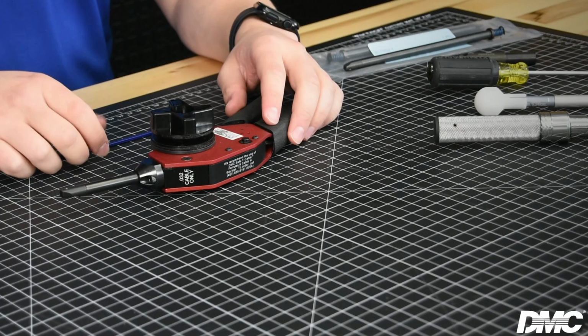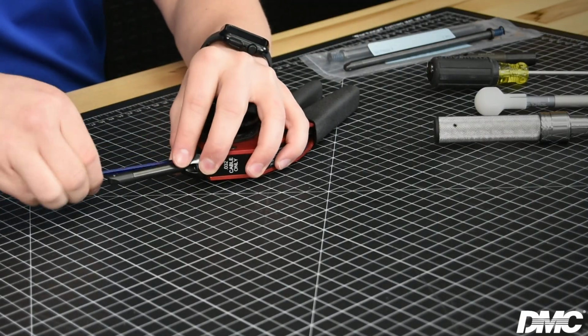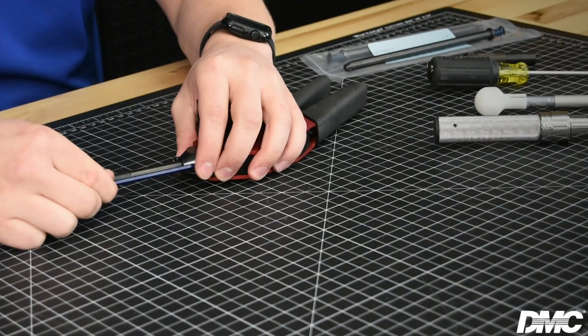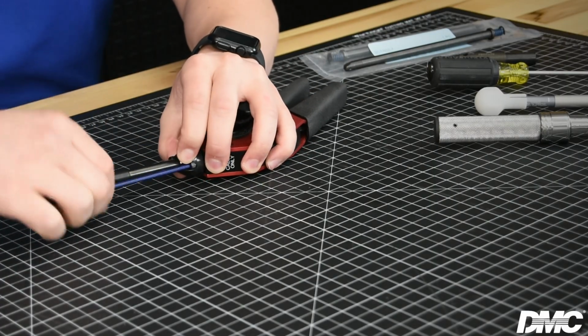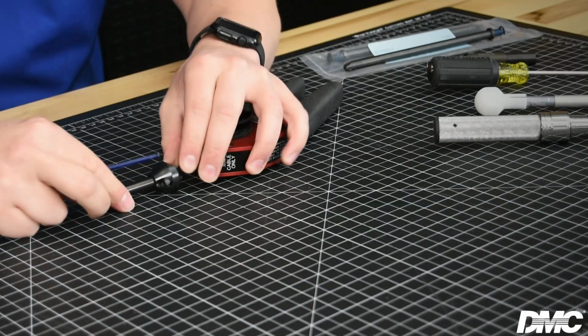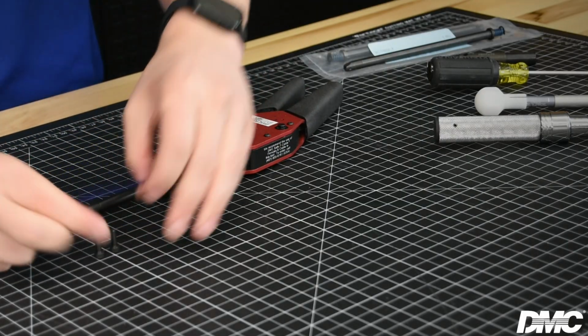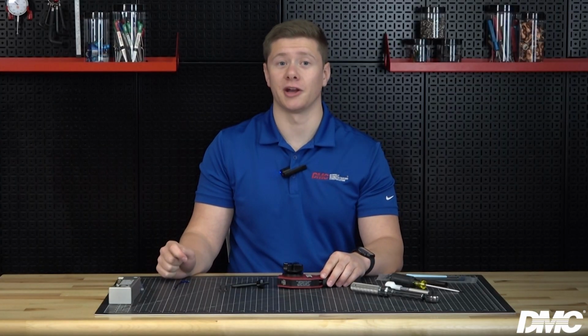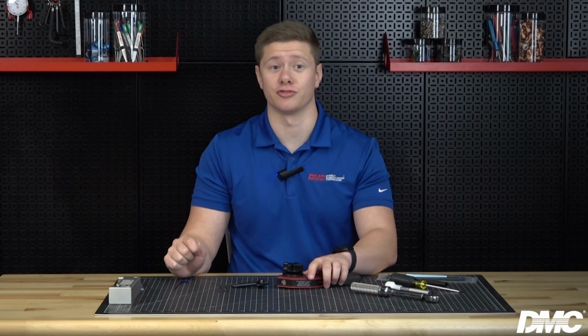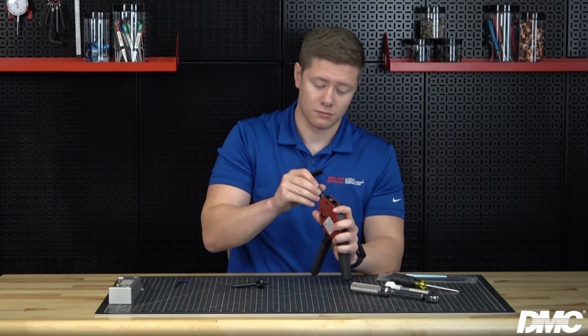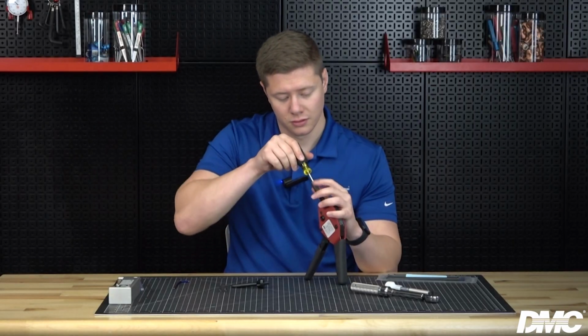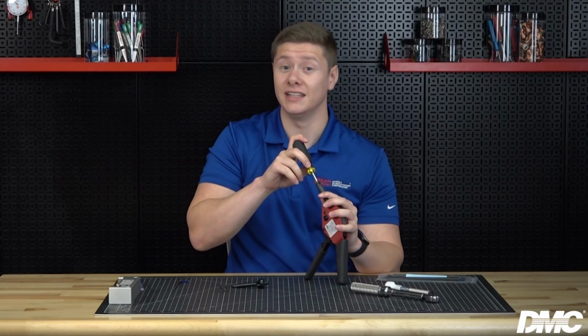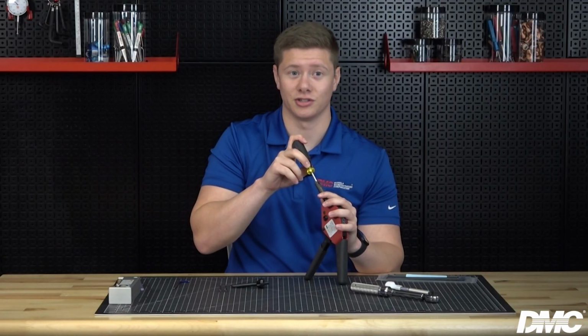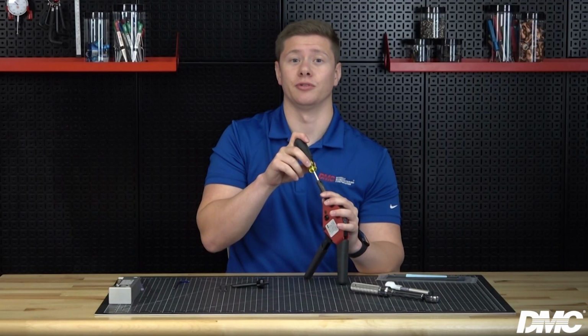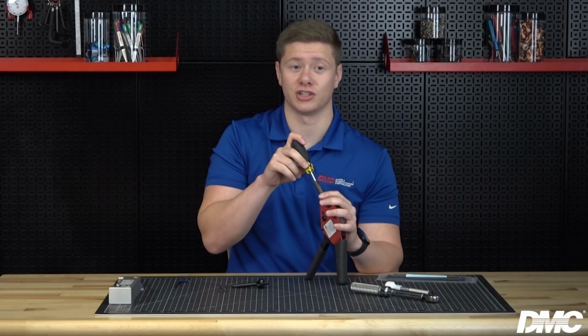To make adjustments to the indenters, remove the nose assembly by removing the two socket head cap screws. Release the jam nut using the spanner wrench and adjust the push rod adjustment screw using the supplied screwdriver. Turn the screw clockwise to decrease the tension. Turn it counterclockwise to increase the tension. After each adjustment, tighten the jam nut using a spanner wrench and a screwdriver to hold the adjustment screw stationary.